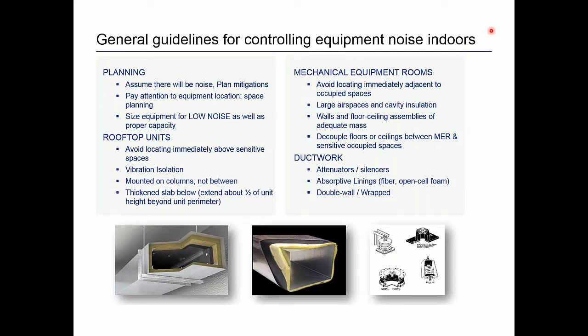What can you do to reduce indoor noise from HVAC systems? Number one: if you have the opportunity, planning is your best friend. You must assume there will be noise and plan mitigations in advance. Pay attention to equipment location in your space planning and size your equipment for low noise as well as proper capacity. A low-noise unit will do you far more good once installed than trying to retrofit a noisy one. For rooftop systems, avoid locating units immediately above sensitive spaces like offices or doctor's examination rooms. Use vibration isolation, mount the mass and weight over building columns rather than in between them, and add a large thick mass on which the unit sits — it blocks the vibration path.